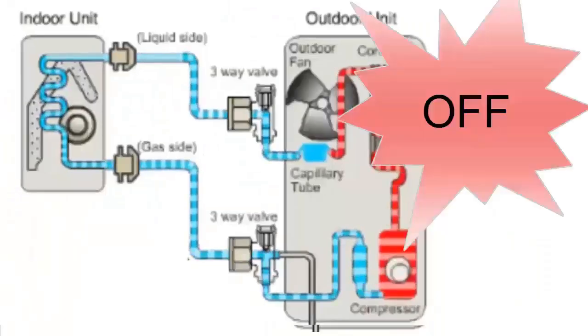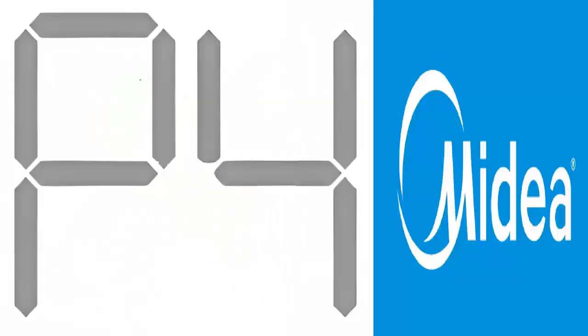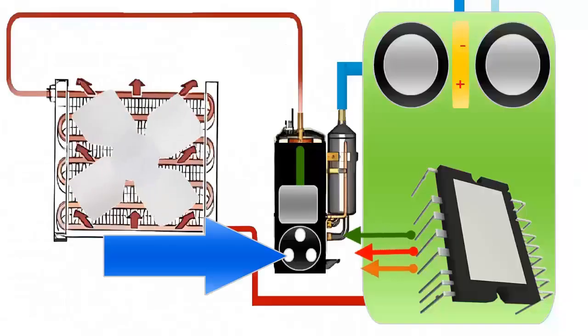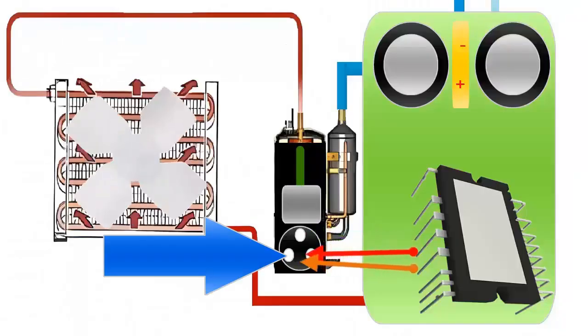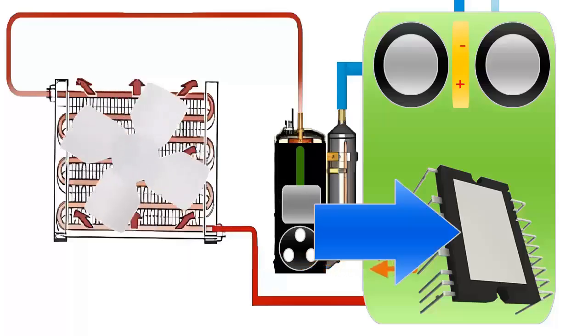Code P4 generally indicates an inverter compressor drive error. Recommendations: A. Check the electrical connections of the compressor. B. Turn off the unit and check the inverter module, as we will show at the end of the video.